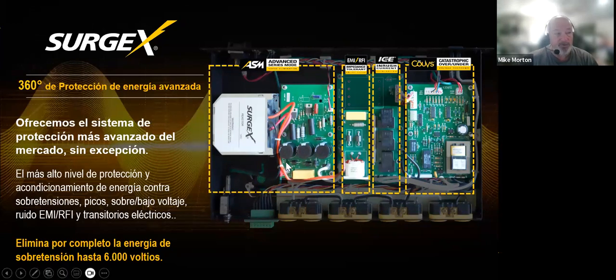When we go into this board with this series of rectifiers and capacitors, this area will eliminate any of the low residual let-through voltage that might have come through accidentally. So now we've eliminated in this reactor area all high frequency, and now we've eliminated all low frequency. At this point, we have zero let-through voltage. It then goes through the secondary area, which is called EMI RFI filtration, or noise filtering. We know that noise is a big problem that can cause a lot of problems as well. With that being the case, we try to filter anywhere from 20 hertz to as high as 20,000 hertz. That's about as far as we can go without actually interfering with data. So at that point, we've eliminated as much noise as absolutely possible.